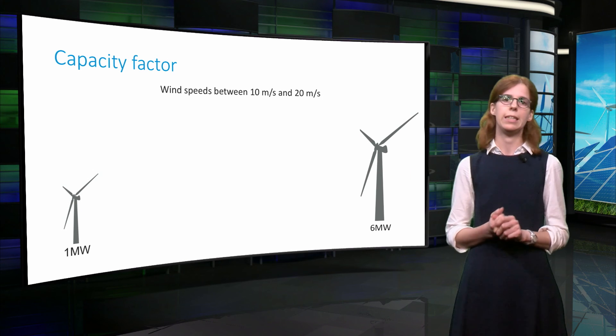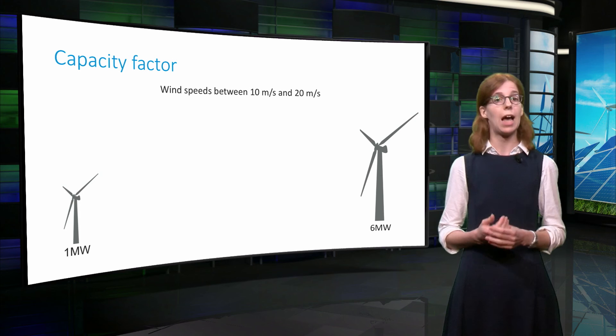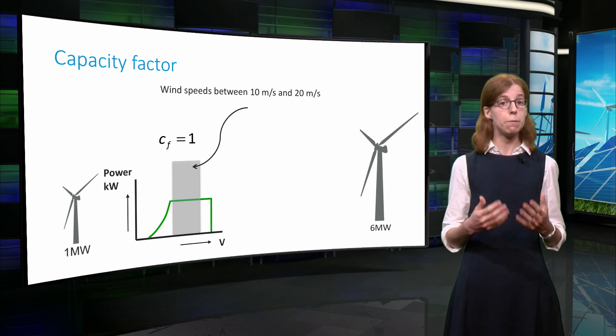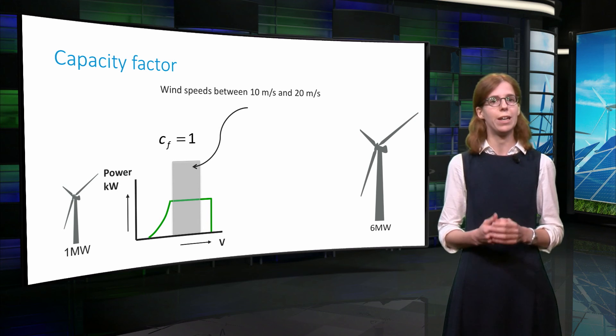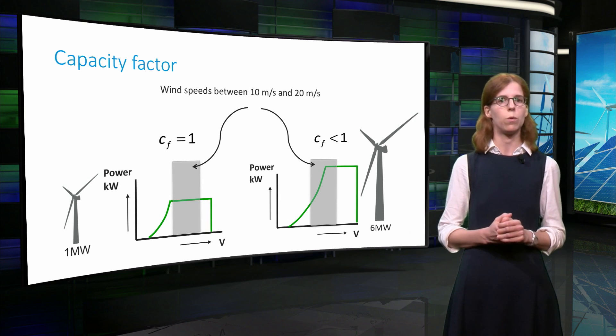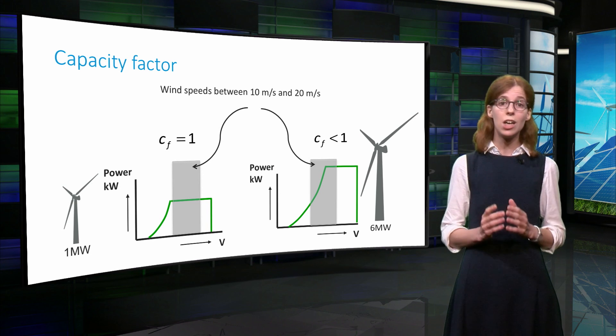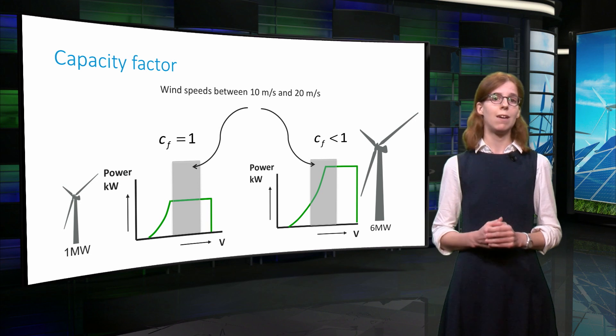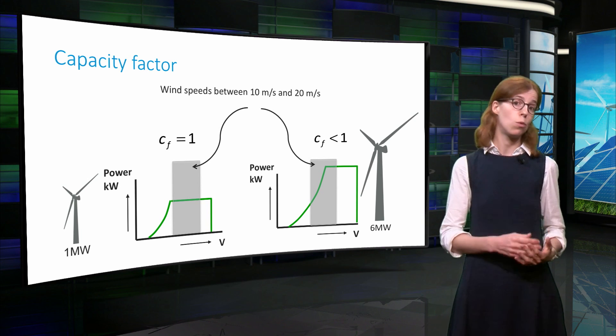This is illustrated by this slide. Imagine that the wind speed varies between 10 m/s and 20 m/s at a given location. Placing a 1 MW turbine at this location might mean that it will run all the time at rated power, thus producing 1 MW all year long. By contrast, a 6 MW turbine might not be running at rated power all the time, so its capacity factor will be lower. However, when it does run at full power, it will produce 6 MW. So despite its lower capacity factor, the overall power produced by the 6 MW turbine might well be larger than that of the 1 MW turbine.